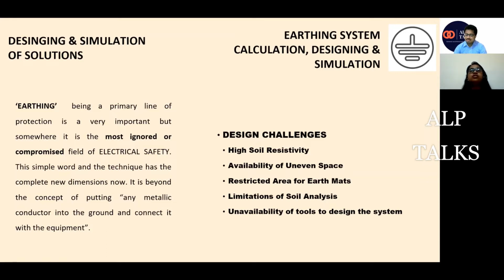And of course, there was unavailability of proper tools too. Initially, all the calculations were done by Excel sheets, and they were manual calculations. Obviously, they had some restrictions. Also, there were chances for mistakes, because of human errors. Due to this, either we were over designing the system as per the actual requirement, or we were under designing the system, and at the time of installations we were not able to achieve the values.